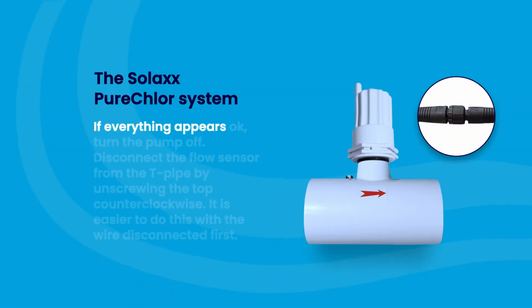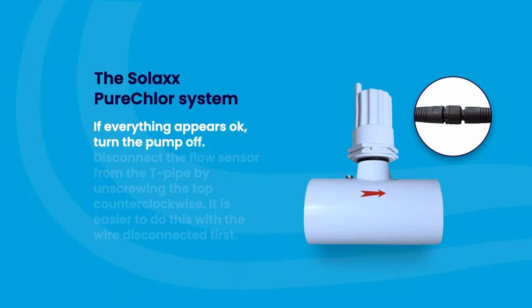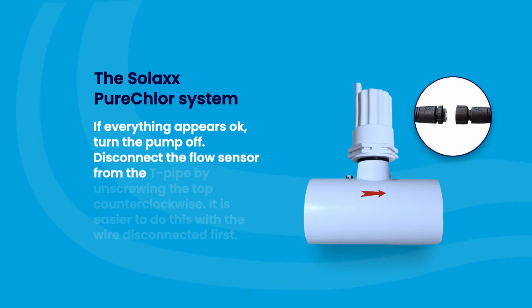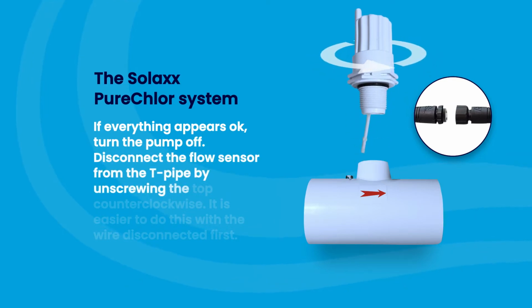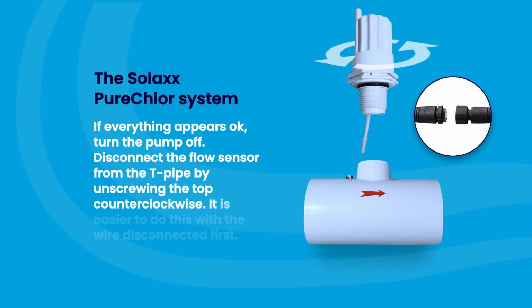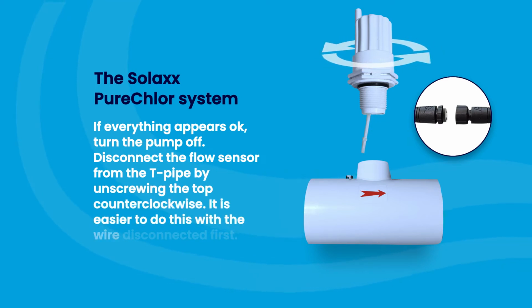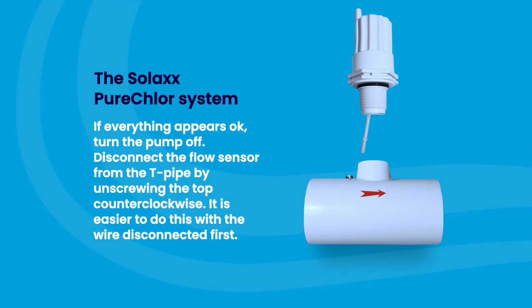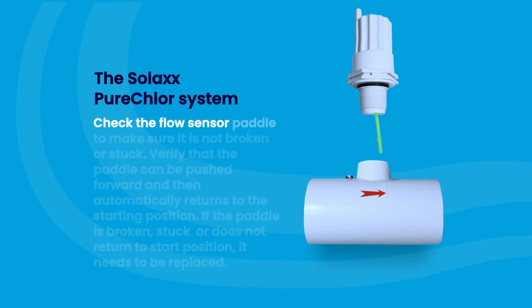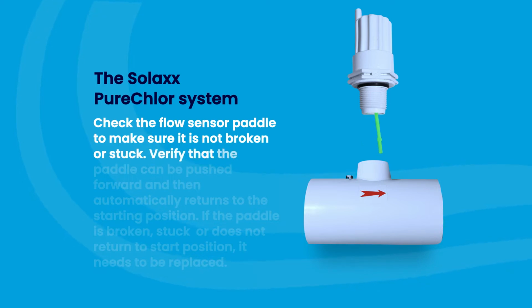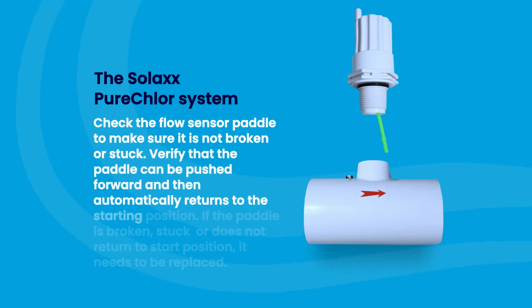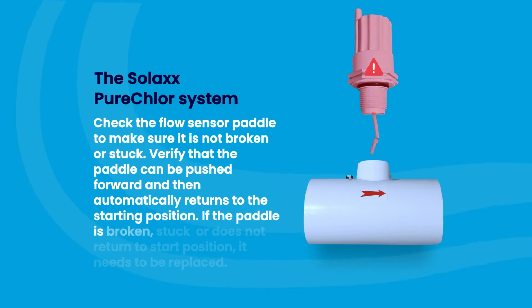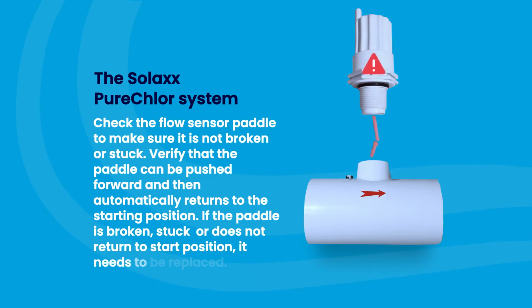If everything appears okay, turn the pump off. Disconnect the flow sensor from the T-pipe by unscrewing the top counterclockwise. It is easier to do this with the wire disconnected first. Check the flow sensor paddle to make sure it is not broken or stuck. Verify that the paddle can be pushed forward and then automatically returns to the starting position. If the paddle is broken, stuck, or does not return to start position, it needs to be replaced.